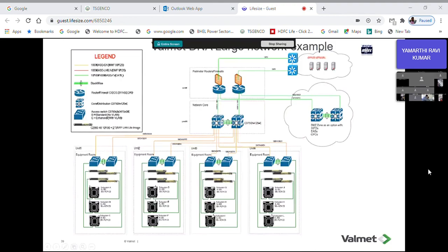As I mentioned earlier, this is called the DMZ zone, where we keep our information server and whatever external interfaces are there. All this will happen through this zone only, which is our demilitarized zone. This is a zone which will interact with the outside world. So the info server also will be placed in this zone, and it can provide the reporting and analysis functionality to the office network through the web browser.